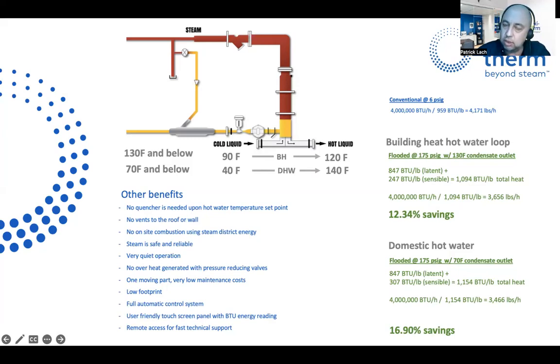So if your temperature set point is 180 and the temperature is 160, well, there's no way condensate will be dumping at 140. Right? So it all depends on your temperature set point, not necessarily the steam pressure. No vents to the roof or the wall. So that I cannot explain because we're running out of time, but there's absolutely no vents needed.